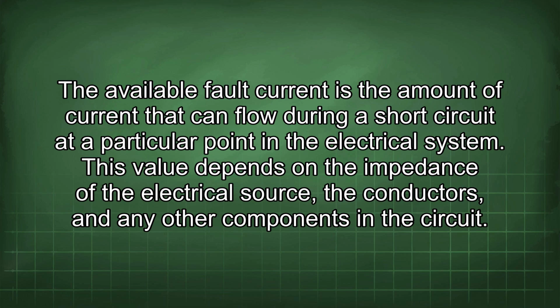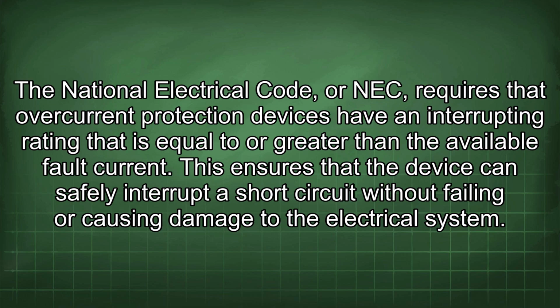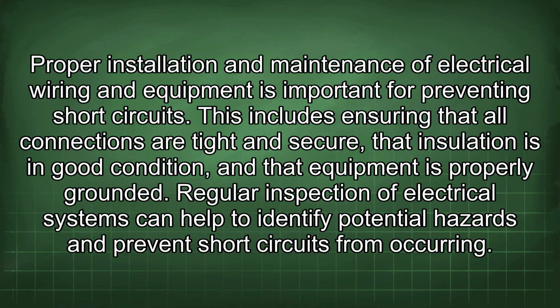The National Electrical Code, or NEC, requires that overcurrent protection devices have an interrupting rating that is equal to or greater than the available fault current. This ensures that the device can safely interrupt a short circuit without failing or causing damage to the electrical system. Proper installation and maintenance of electrical wiring and equipment is important for preventing short circuits. This includes ensuring that all connections are tight and secure, that insulation is in good condition, and that equipment is properly grounded.